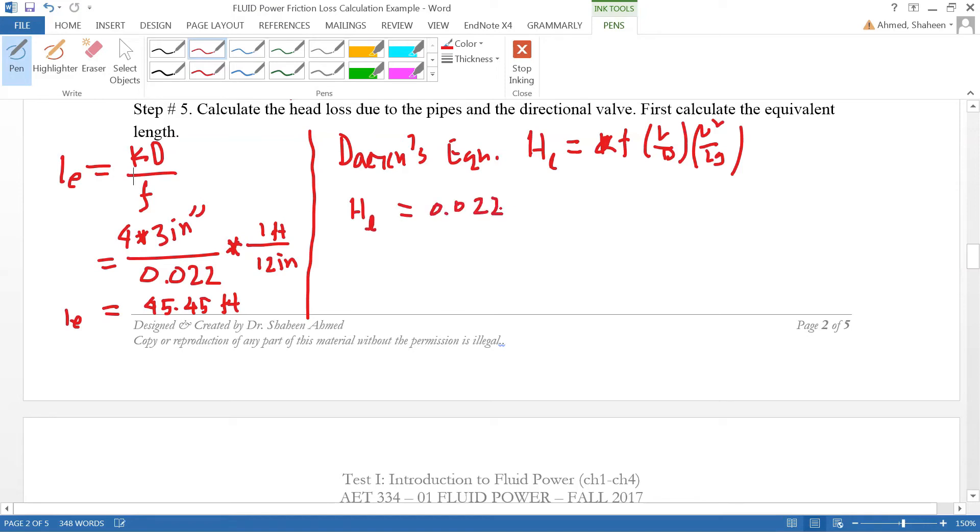.022 times the total length - the pipe is 120 feet plus the equivalent length of 45 feet which has equivalent loss to the directional valve. Then divide by 3 inch diameter. The numerator is in feet, the denominator is in inches, so we have to convert that.